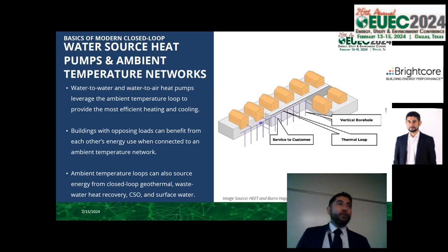Before, ground source heat pumps used what we called open hole or open well—basically tapping an aquifer. Notice I keep saying borehole and not well; for permitting purposes, we are not injecting, we are not pumping, we are leaving it alone. It's an overgrown soil nail. If you're familiar with civil engineering, when you grout you maintain consistency. This is thermally enhanced grout, which gives enhanced thermal conductivity so you can move heat quicker, without relying as much on Darcy flow or permeability.